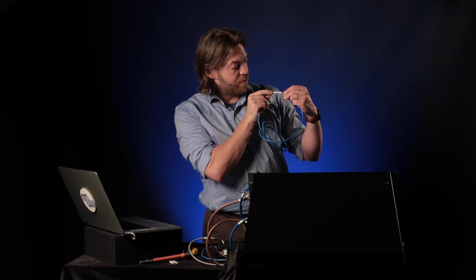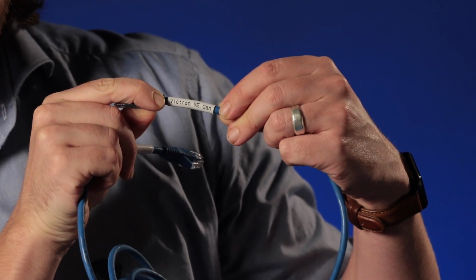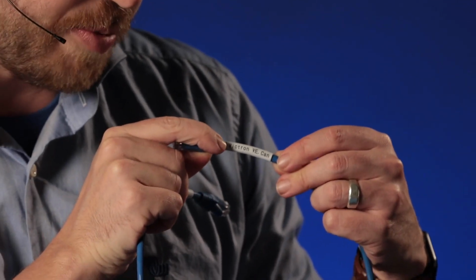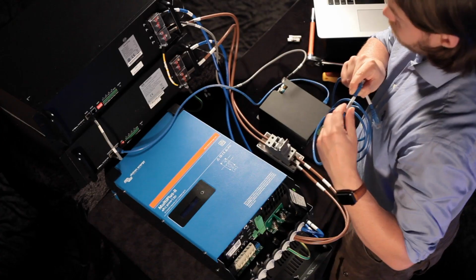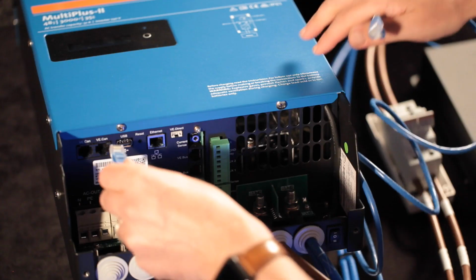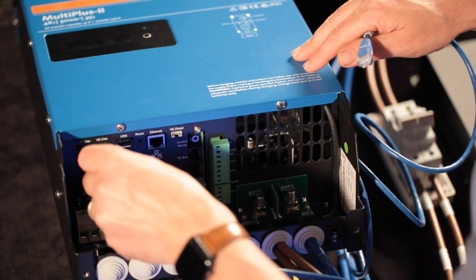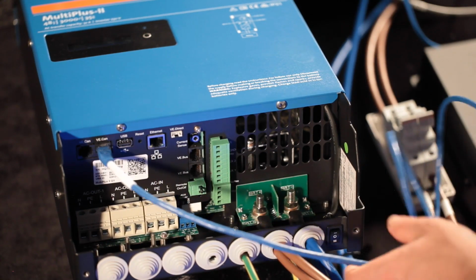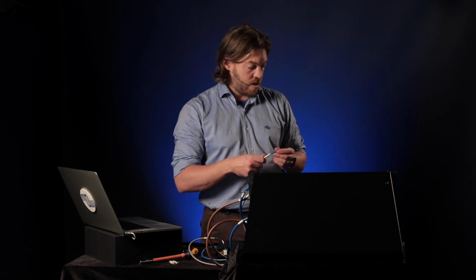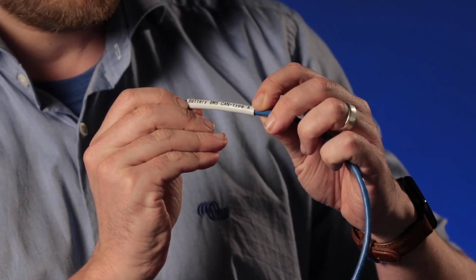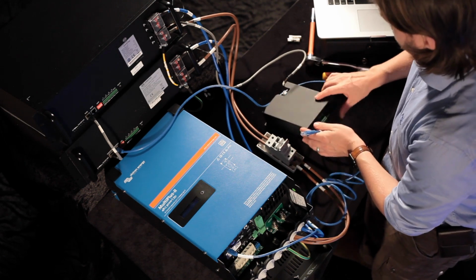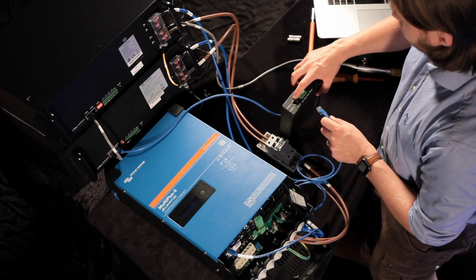You'll see on the cable, one end is labelled Victron VE CAN. That end goes into the MultiPlus 2GX VE CAN port. There are 2 VE CAN ports on the MultiPlus 2GX, and it can go into either of them. The other end is the battery BMS CAN type A cable, which goes into the CAN port on the front.